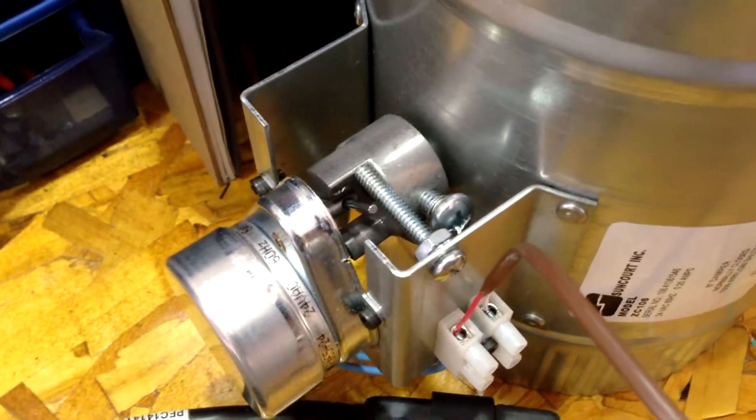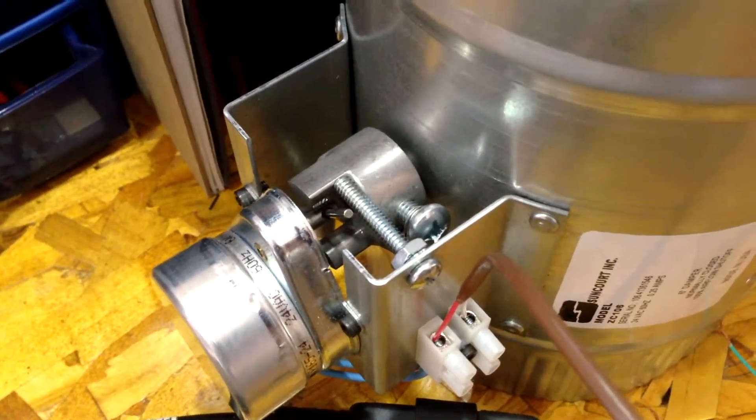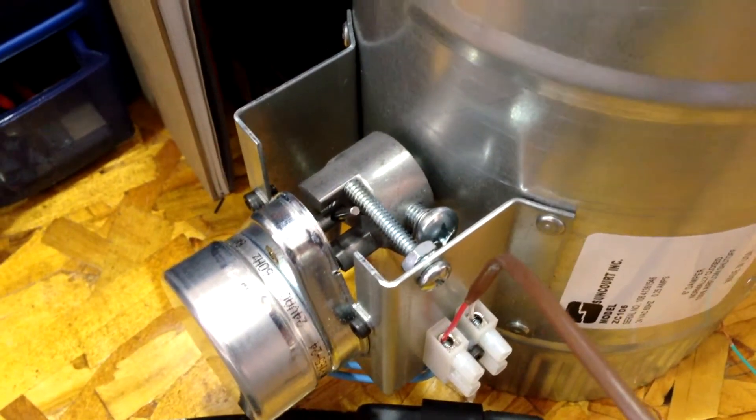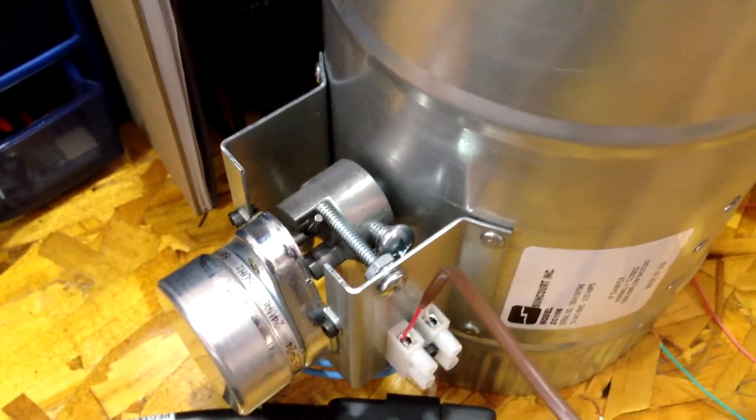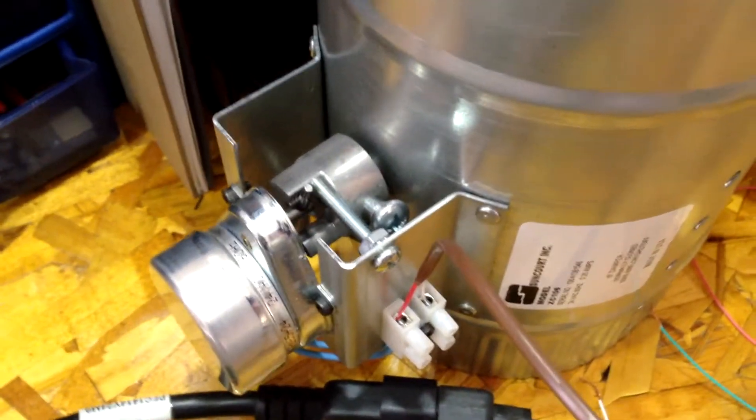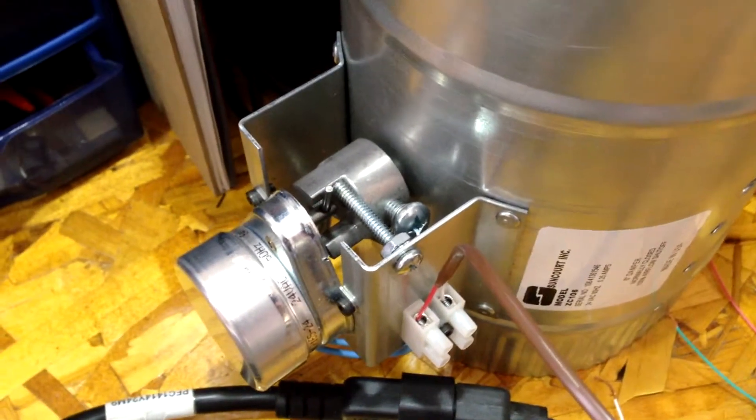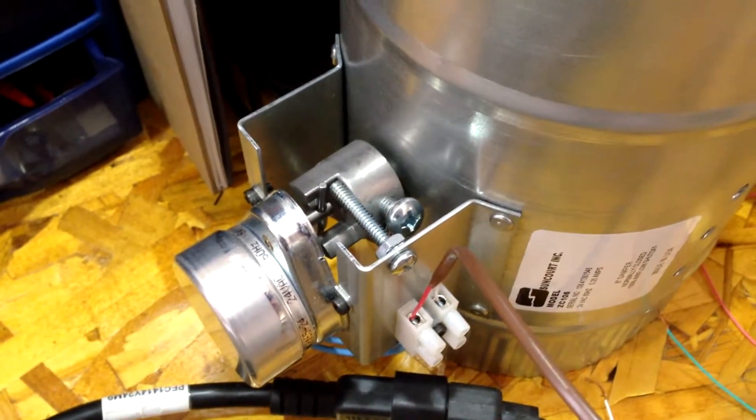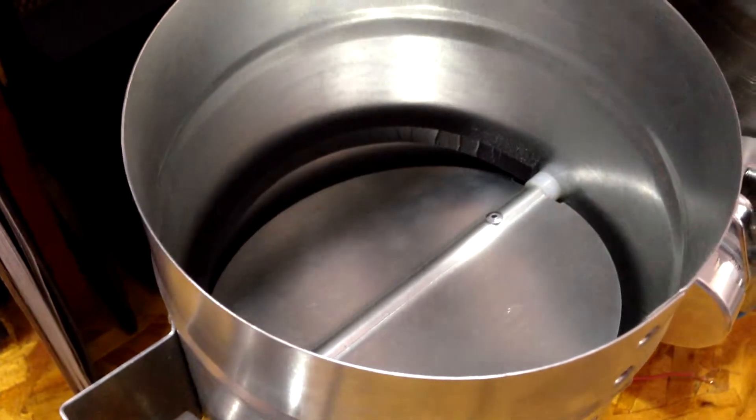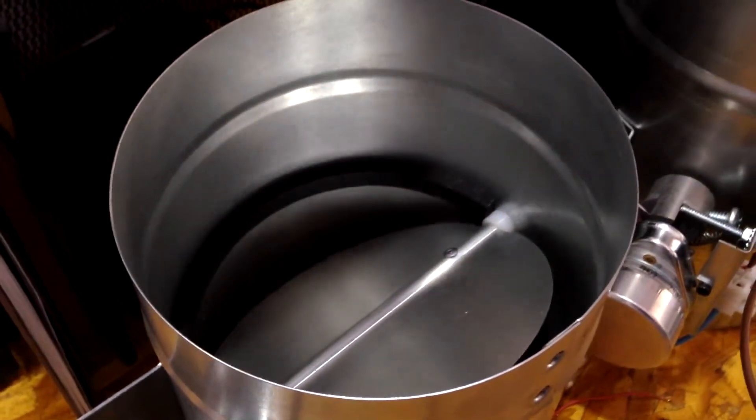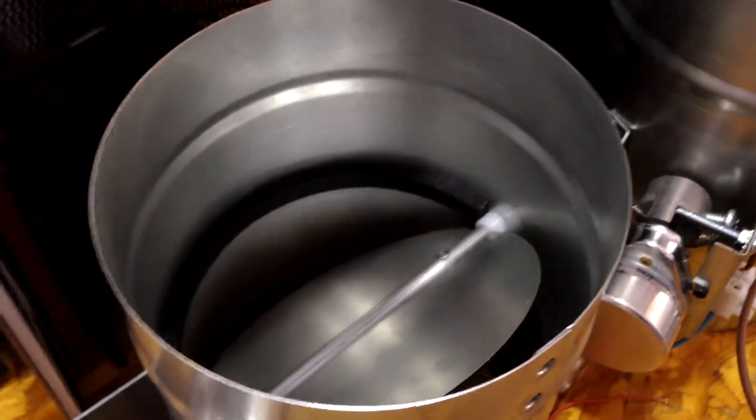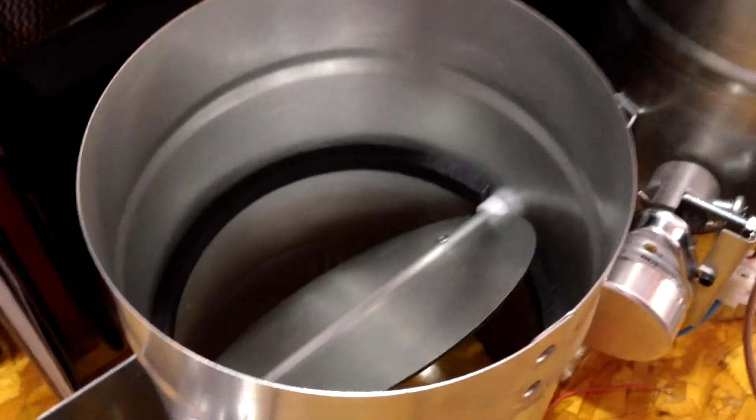It's actually not going to do anything else. It's not turning the fan on yet or anything. It's going to give it 35 seconds to open the damper fully so that we're not trying to blow the air into a wall.